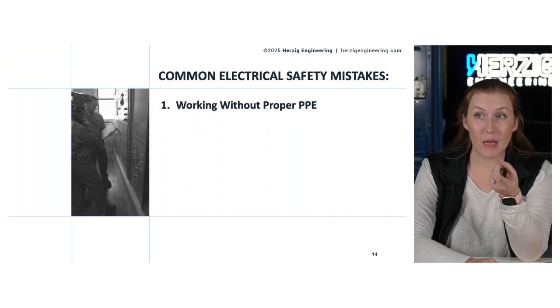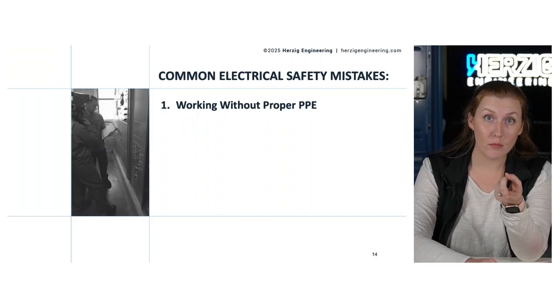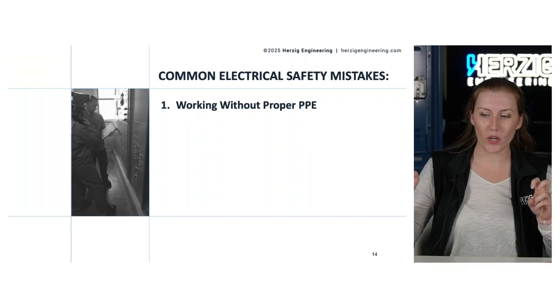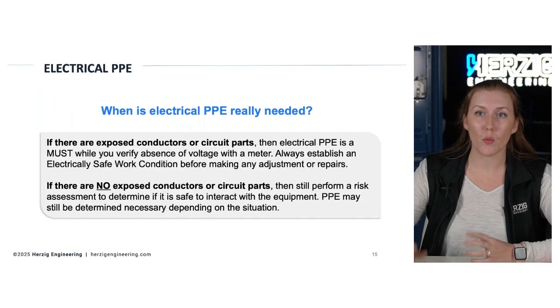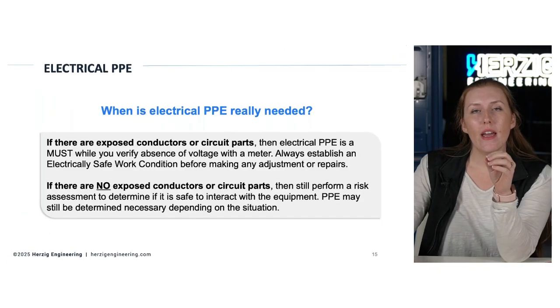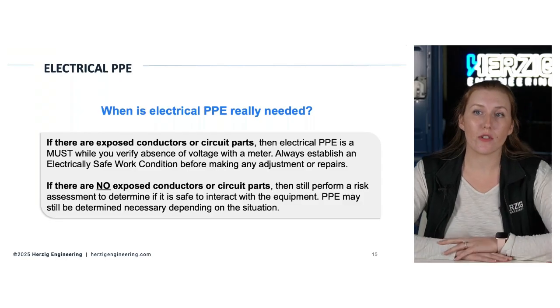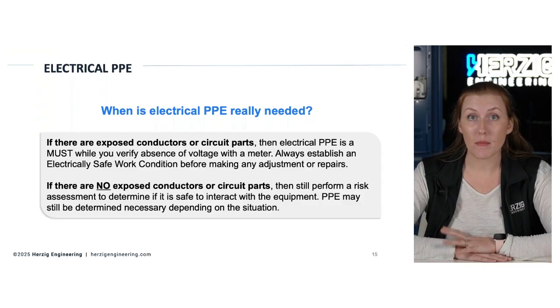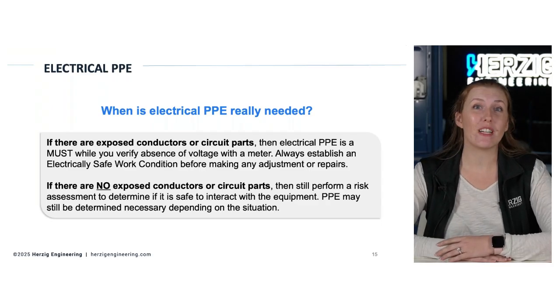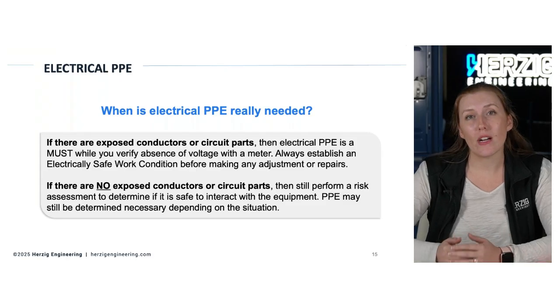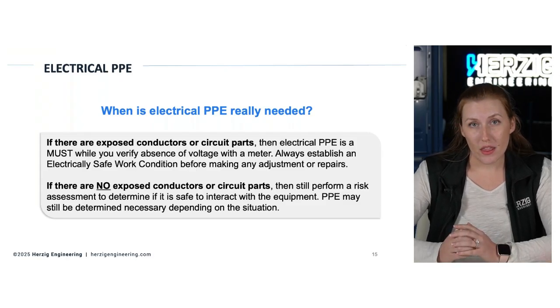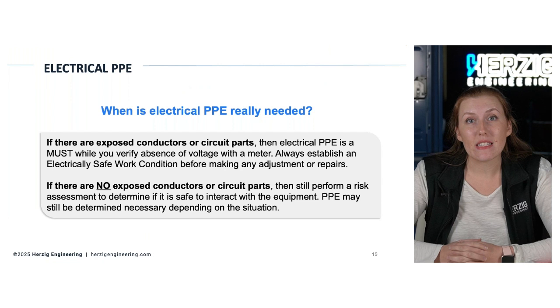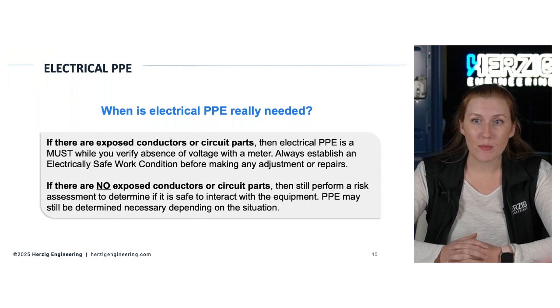First of all, maybe they don't even realize PPE is needed because they think, well, I'm not doing energized work. Let's look at this: when is electrical PPE needed? If there are exposed conductors or circuit parts, then electrical PPE is a must - even to verify absence of voltage, troubleshoot, visually inspect, or perform infrared scans. Anytime you're crossing those boundaries, people in hazardous areas need to be protected if it's exposed.